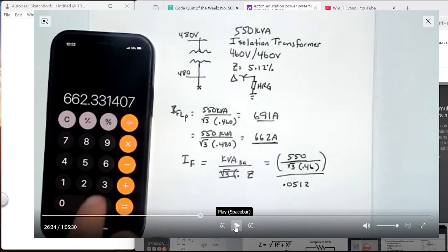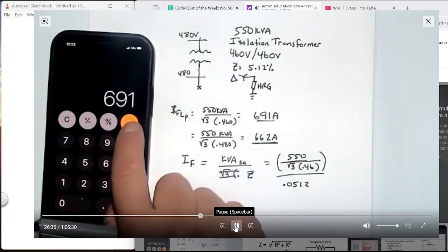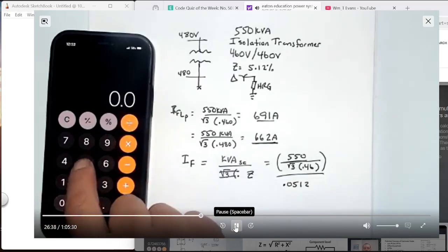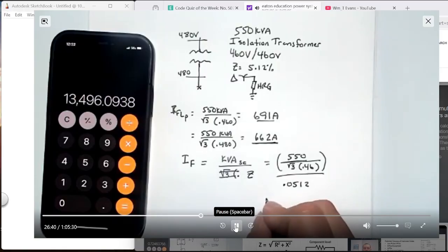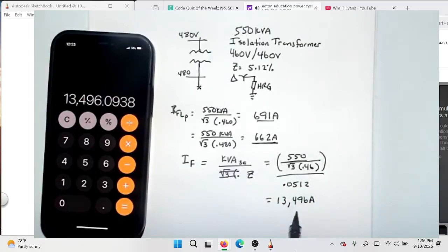Okay, we got it? 691 divided by 0.0512. And that's going to work out to be 13,496 amps. That's our fault current. And honestly, again, these are estimated values. So let's talk about that for a minute.